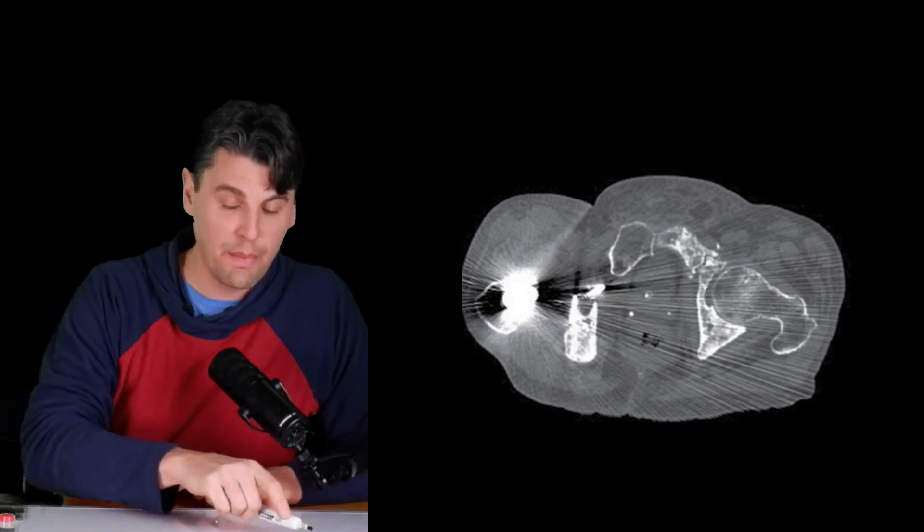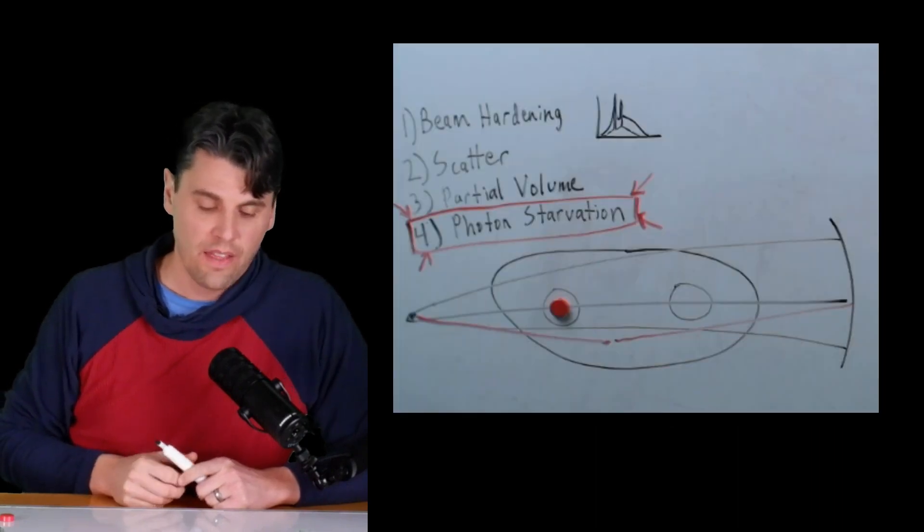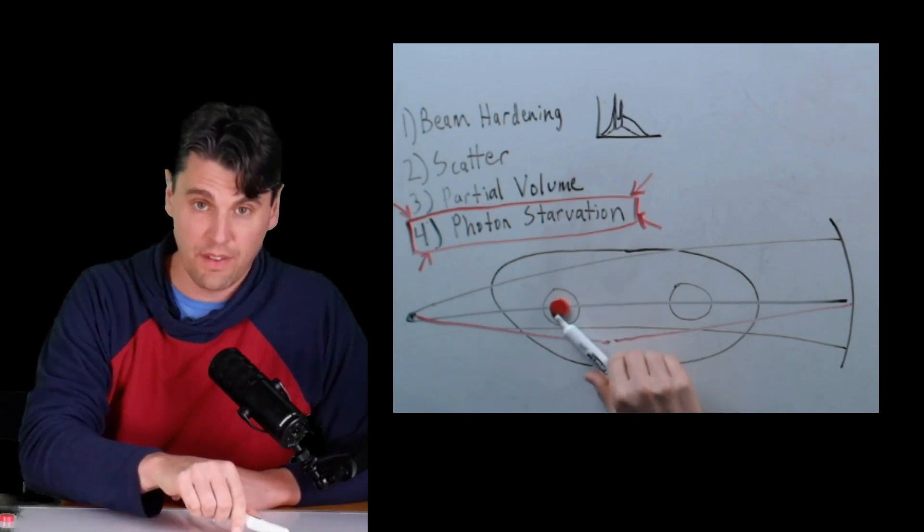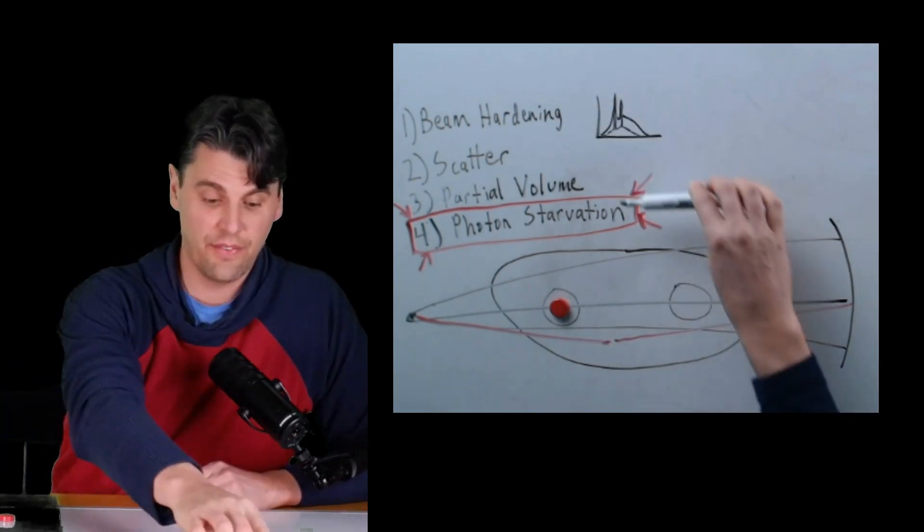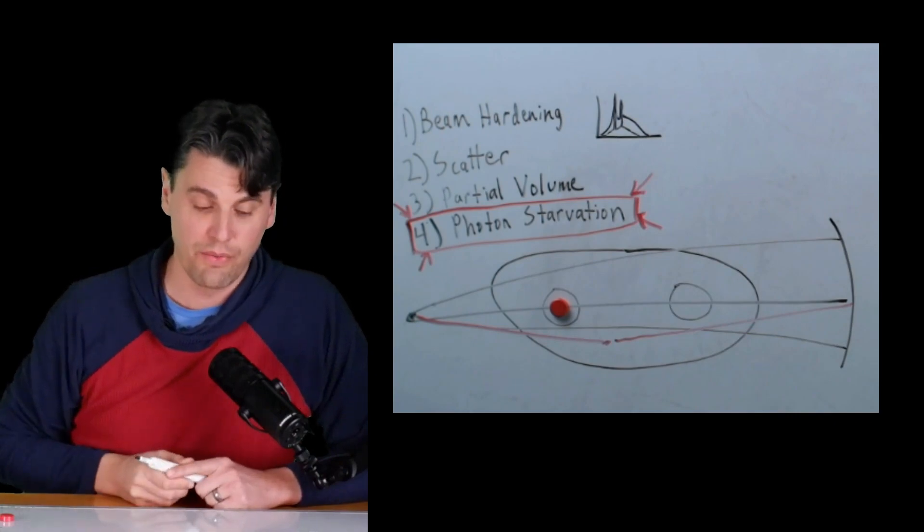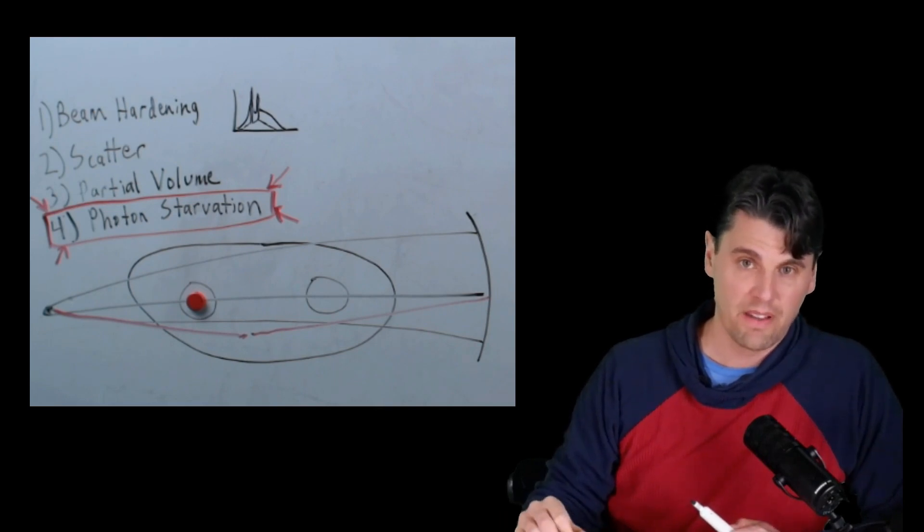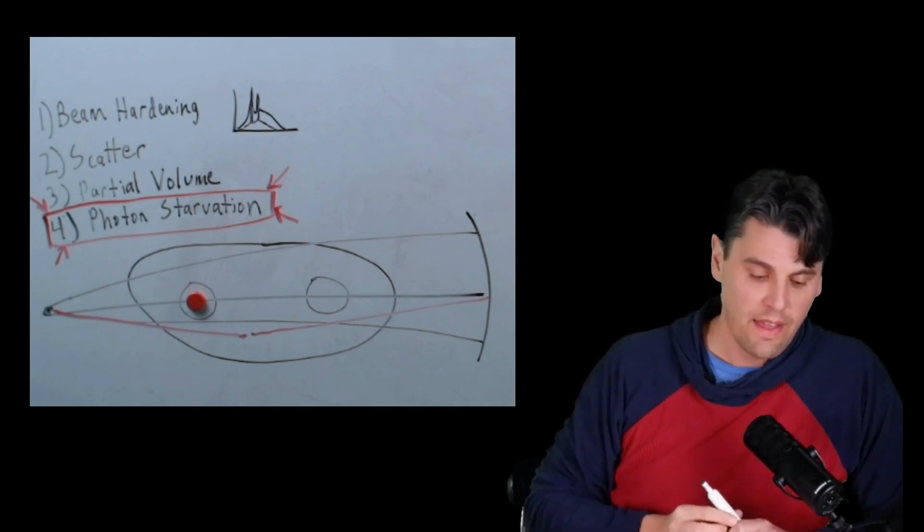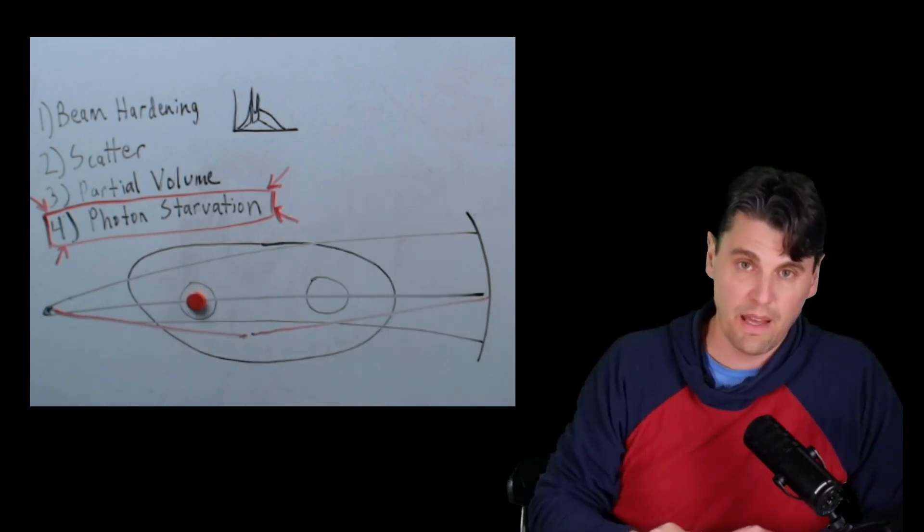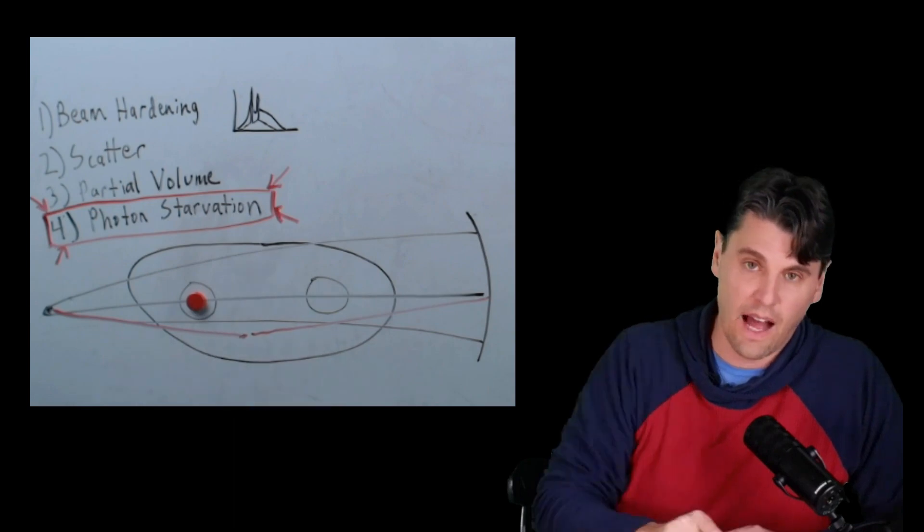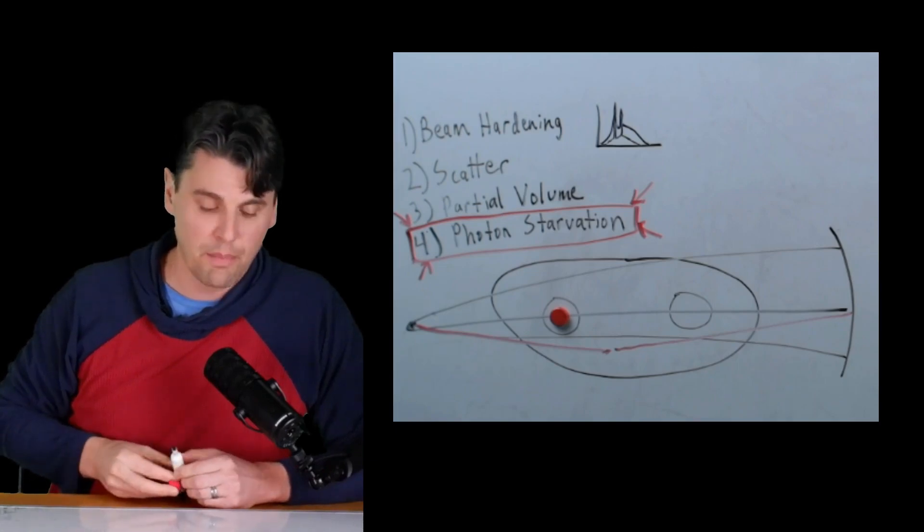If you have a single metallic object which is very highly attenuating, what you're generally going to see is artifacts that are originating from the area of this metallic object and will come off in streaks around this metallic object. That's due to these different causes here, and especially due to photon starvation. This is made even worse in the case that you have multiple highly attenuating metallic objects. So if you have just one object, then you still have relatively good measurements of all the different view angles in your projection space, as long as you're away from the metallic object a little bit. So you'll get some streaks coming off, and they'll start to corrupt things around that metallic object and make streaks around it.